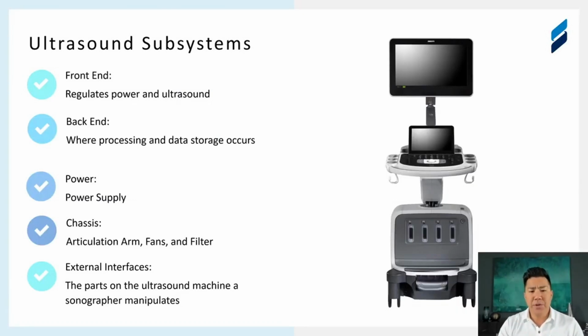So generally in ultrasound, we think of ultrasound systems in really 5 distinct categories. There could be some parts as they continue to consolidate functions onto PCBs that, in legacy machines, may have been separated. Now they're starting to combine them together. There's some gray area here, but in general, all machines have a front end, which regulates power of the ultrasound machine to the probes. So this is the part of the subsystem that really takes the transducer and gives it power to emit sound from the crystal, and then if that crystal returns information, it will take that information, digitize it, and give it to the computer.